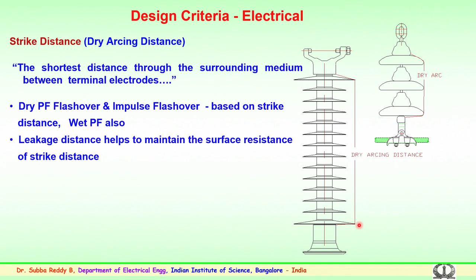Similarly, dry power frequency, PF is the power frequency flashover, and impulse, again impulse could be lightning, which is a double exponential waveform of 1.2 by 50, or a switching waveform of 250 by 2500. The impulse flashover or the power frequency flashover tests are conducted based on this strike distance, that is, the metal to metal portion of the insulator assembly. Similarly, for wet power frequency flashovers also. So, wet power frequency or dry power frequency, that is at 50 hertz or 60 hertz, both withstand and flashover values are decided with the help of the strike distance, the minimum strike distance to be maintained for any insulator assembly. The leakage distance helps in maintaining the surface resistance of the strike distance. So, this is an important point to be considered.